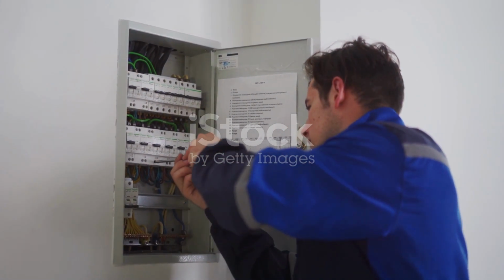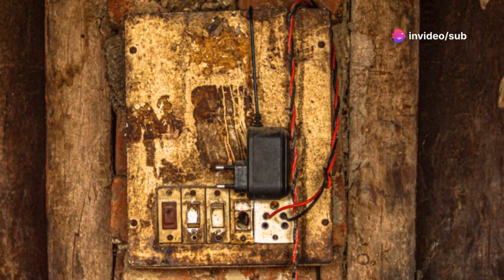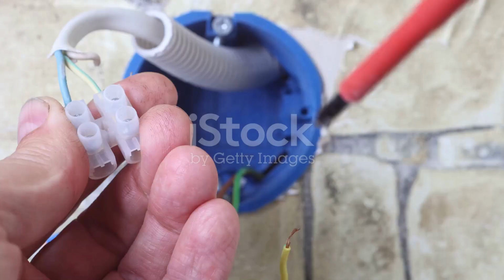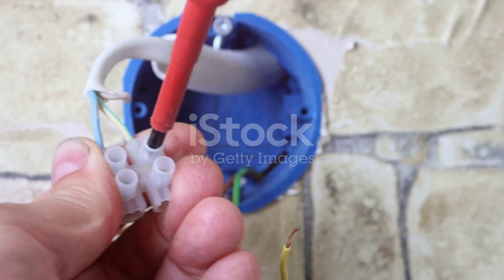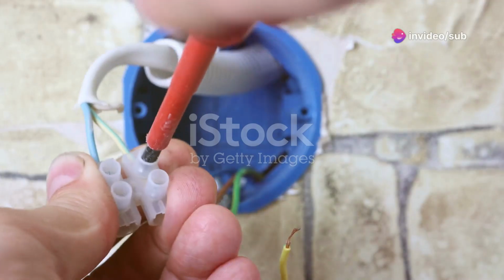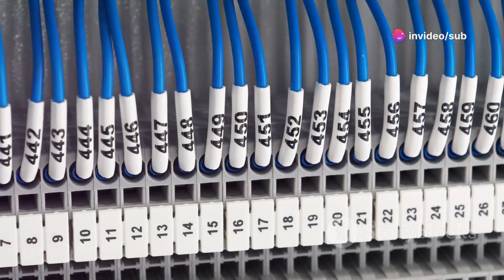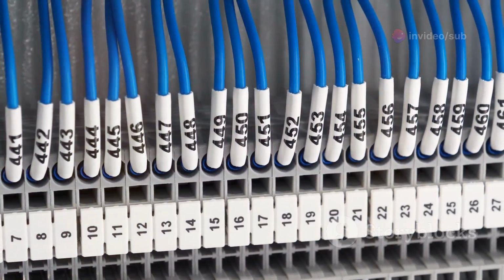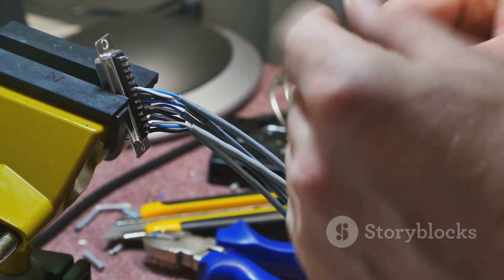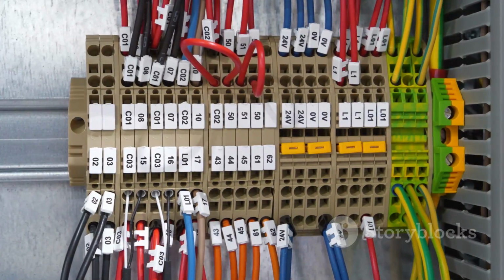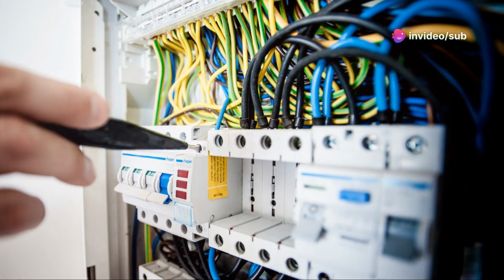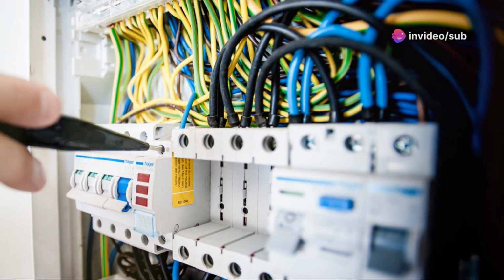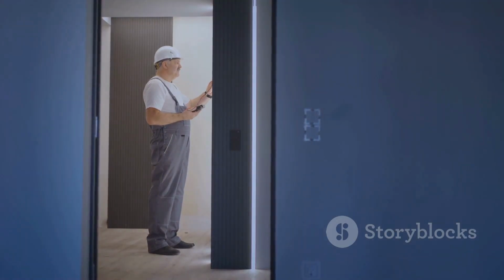To wire a breaker safely, always start by reading the manufacturer's instructions. They'll tell you how many wires you can connect, what sizes are acceptable, and what torque to use. Ignoring these details can void your warranty and risk your safety. Use a torque screwdriver or wrench to tighten terminals to the specified value. Hand tightening is rarely enough. Strip wires to the correct length so no bare copper is exposed, but also so the full conductor fits in the terminal. If you're using stranded wire, add ferrules to the ends. Ferrules keep the strands together and make for a cleaner, safer connection. Before inserting a wire, make sure it's clean, with no corrosion, oil, or debris. By following these steps, you'll reduce the chance of loose wires overheating or accidental shorts.